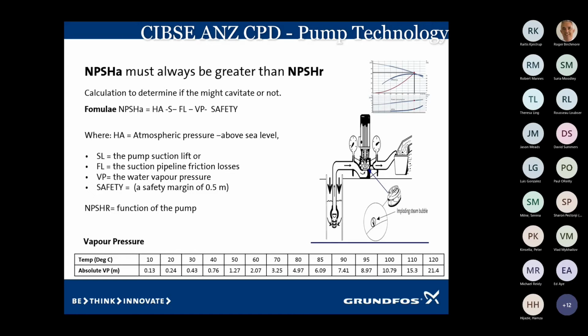And when you have 12 meters, that means that 90-degree water is quite possible. And we can pump water at 90 degrees. And that's the case of the steam boiler. They'll be pumping water around 90 degrees. So they need a much higher head to overcome the vapor pressure, the friction losses, and then the net positive suction head required for the pump.